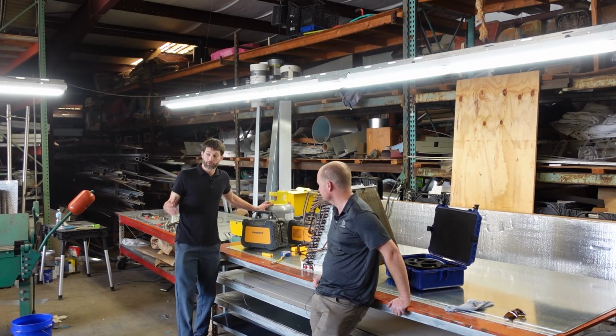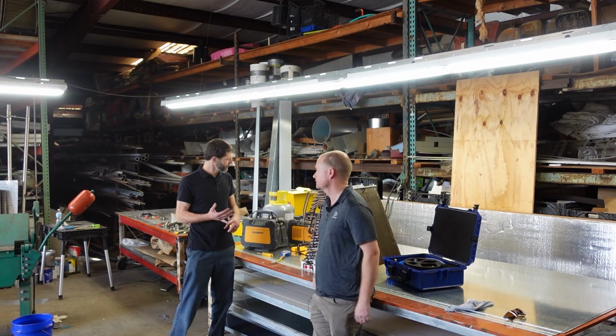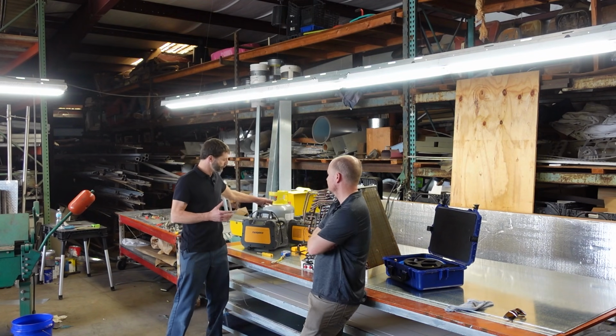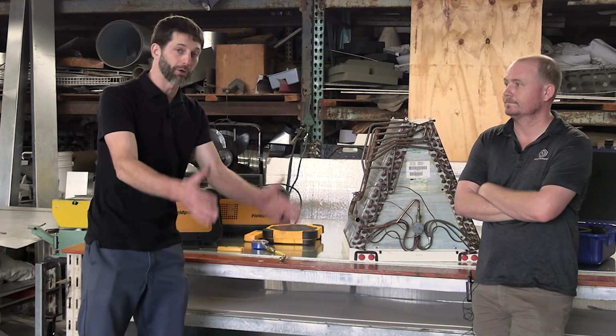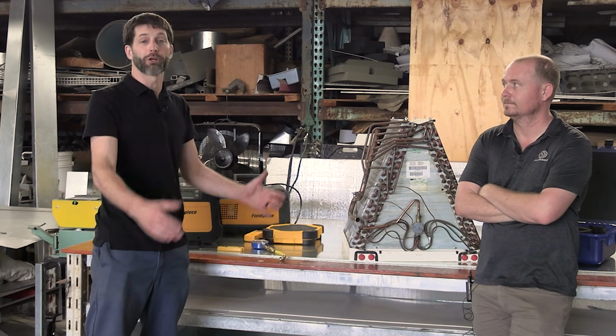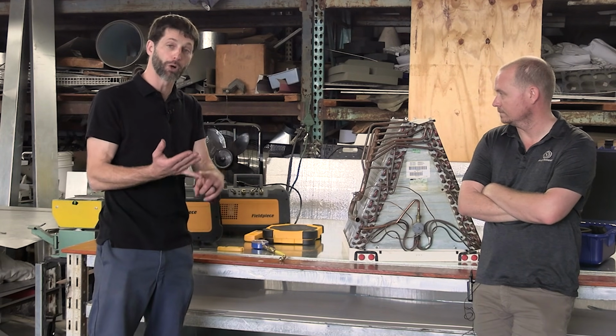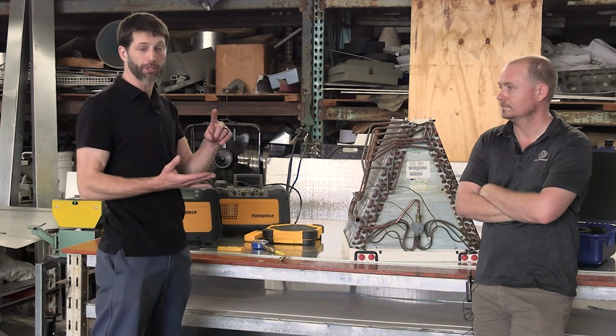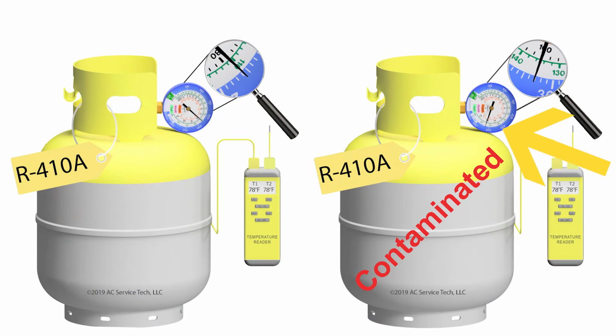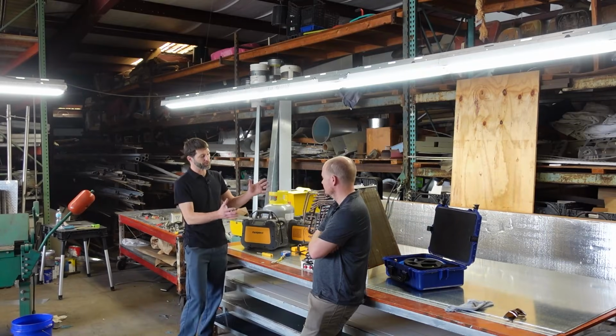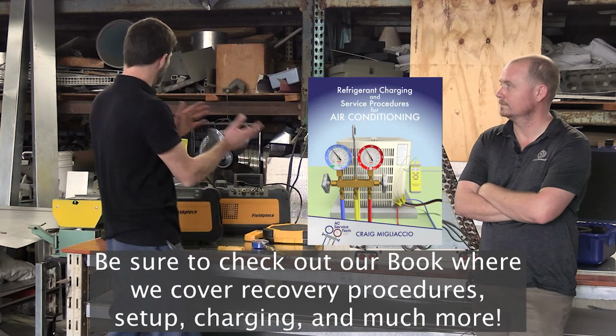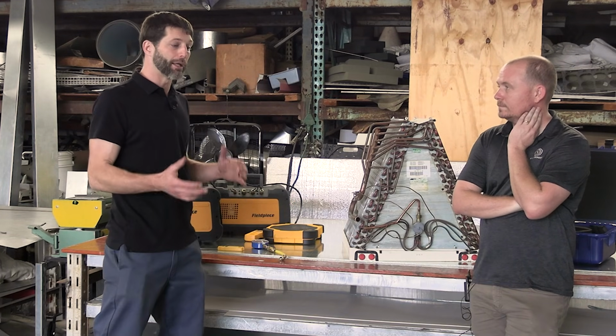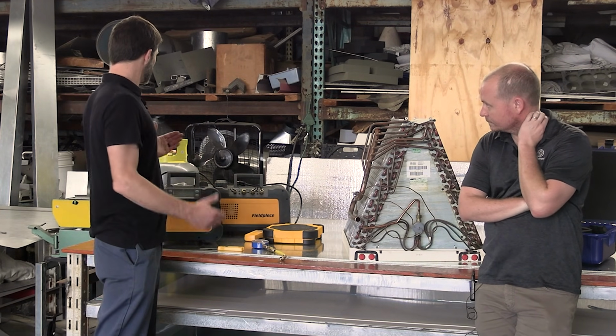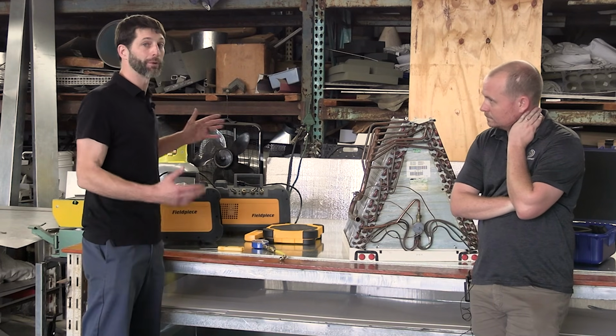So the recovery bottle, it really starts with your recovery bottle. If you're taking a recovery bottle from maybe a fenced-in area within the shop, and maybe you have 10 recovery bottles there, you got to first make sure you know what refrigerant's in that bottle. You also need to make sure if that refrigerant is contaminated. If there's too much air in that bottle, you're not going to be able to pump refrigerant from the unit into that bottle, and basically your recovery machine could go off on high limit, and you really don't want to ever be using refrigerant out of a bottle that's contaminated anyway.